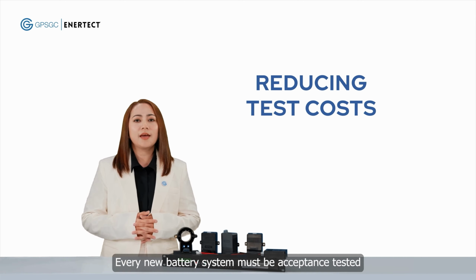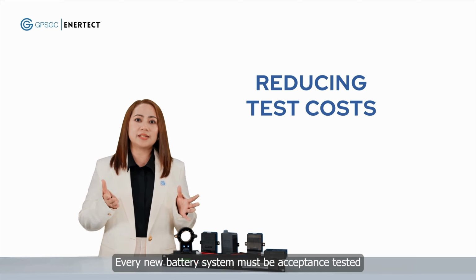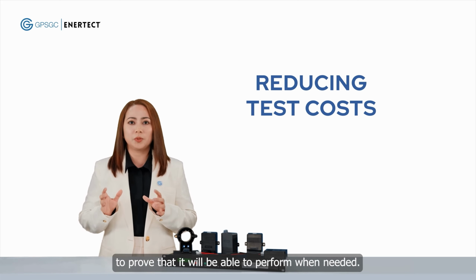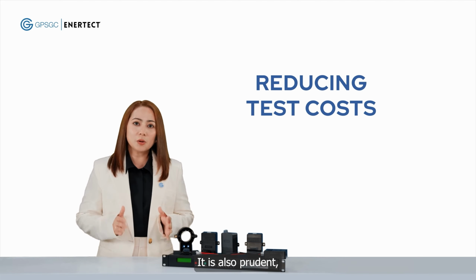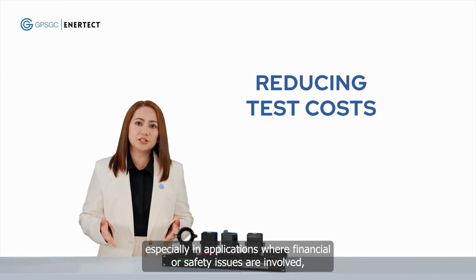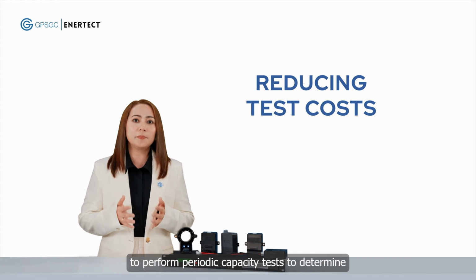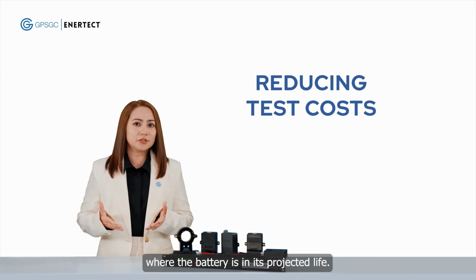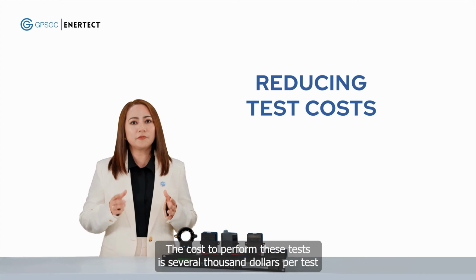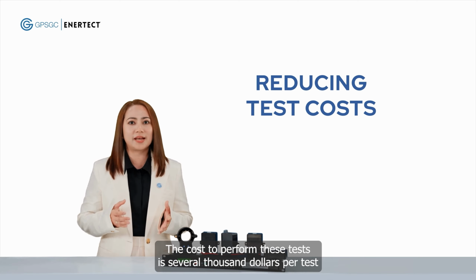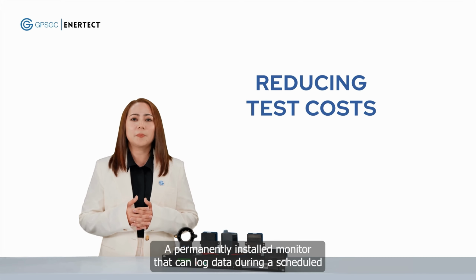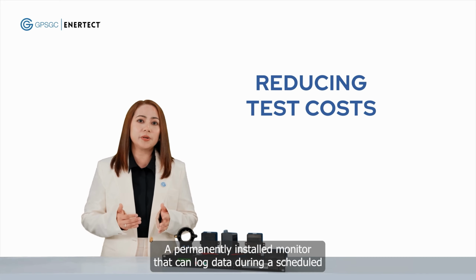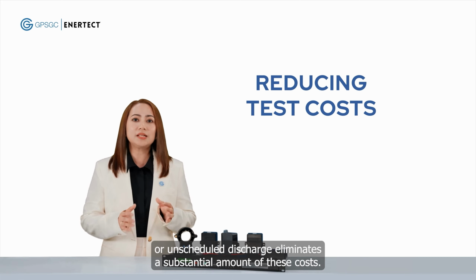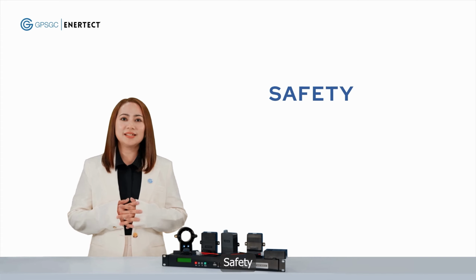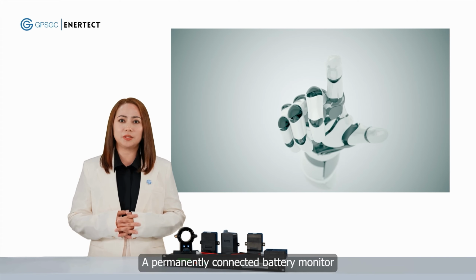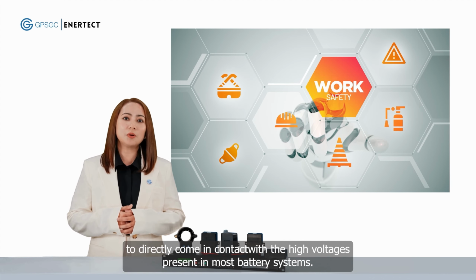Reducing test costs. Every new battery system must be acceptance tested with a capacity test to prove that it will be able to perform when needed. It is also prudent, especially in applications where financial or safety issues are involved, to perform periodic capacity tests to determine where the battery is in its projected life. The cost to perform these tests is several $1,000s per test and requires a lot of setup time. A permanently installed monitor that can log data during a scheduled or unscheduled discharge eliminates a substantial amount of these costs.